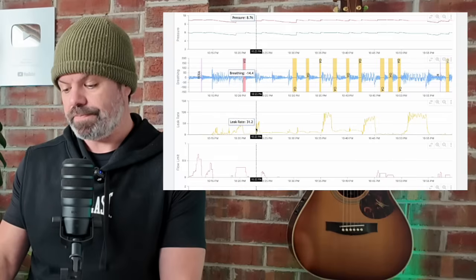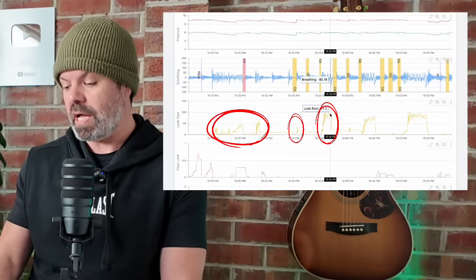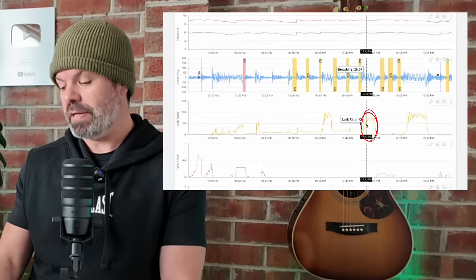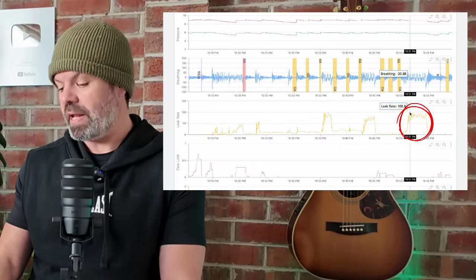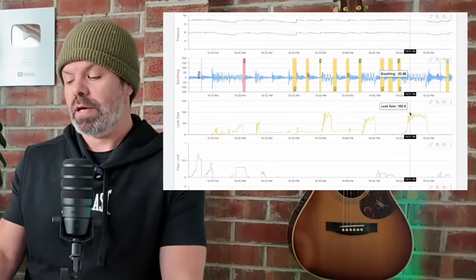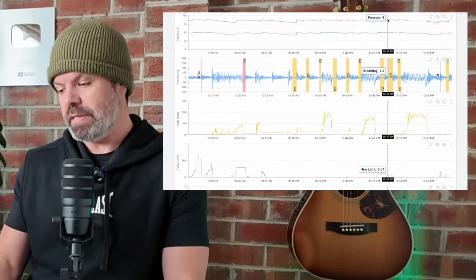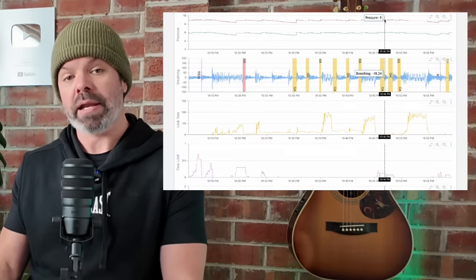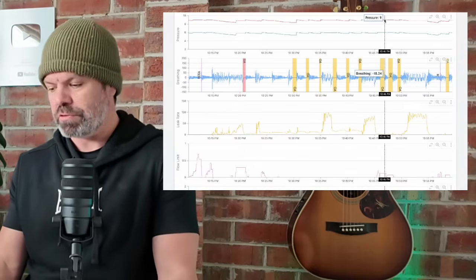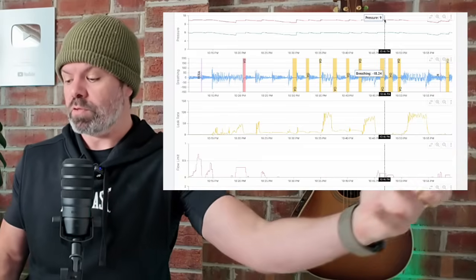And here it is. See these spikes here? Big ones here — look at this, up at 100 liters per minute. 73, once again, a hundred. It's a lot of leak. It's gonna be very difficult sleeping when your mask is leaking like this. And the pressure is up here at nine centimeters, which is only a moderate pressure really. CPAP machines can get right up to 20, bi-levels even higher.